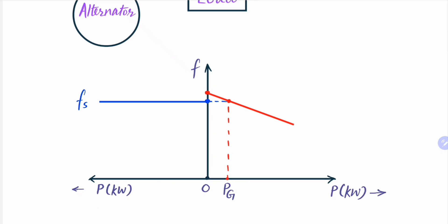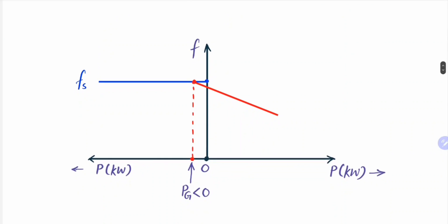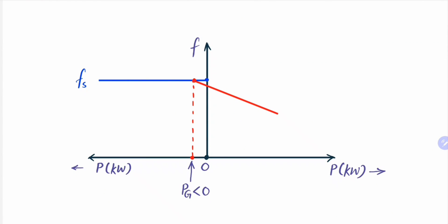The question comes: what if we keep the no-load frequency of this alternator slightly lesser than fs instead of slightly higher? In that case, the point of operation will be such that, since we cannot change the frequency of the infinite bus bar, the active power supplied by the alternator will be negative — it will start consuming active power from the infinite bus bar and behave like a motor. That is why we always keep the frequency of the incoming machine slightly higher than the infinite bus bar frequency.